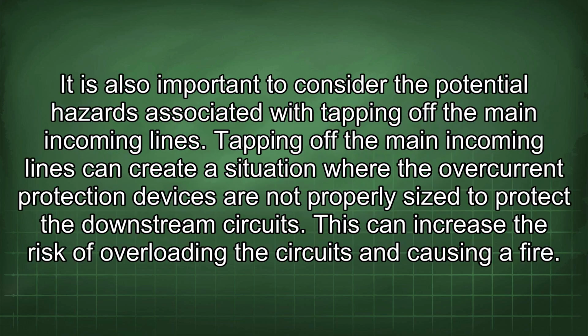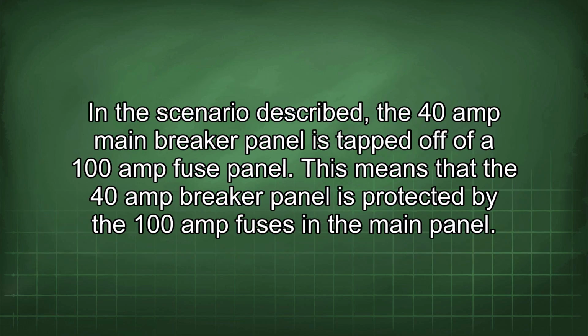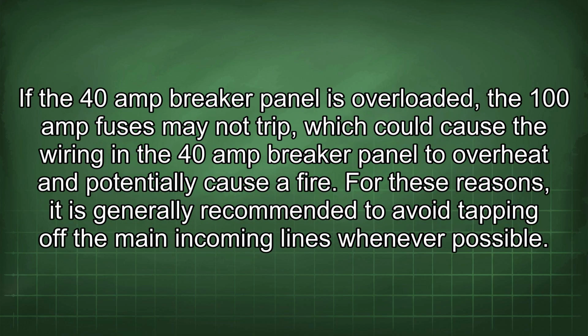It is also important to consider the potential hazards associated with tapping off the main incoming lines. Tapping off the main incoming lines can create a situation where the overcurrent protection devices are not properly sized to protect the downstream circuits. This can increase the risk of overloading the circuits and causing a fire. In the scenario described, the 40 amp main breaker panel is tapped off of a 100 amp fuse panel. This means that the 40 amp breaker panel is protected by the 100 amp fuses in the main panel. If the 40 amp breaker panel is overloaded, the 100 amp fuses may not trip, which could cause the wiring in the 40 amp breaker panel to overheat and potentially cause a fire.